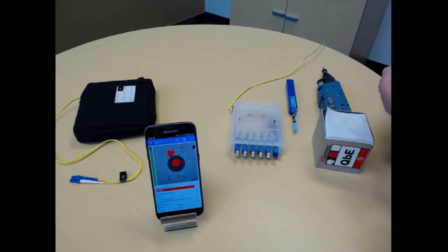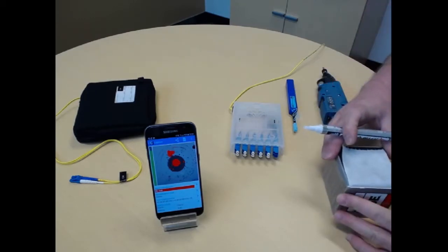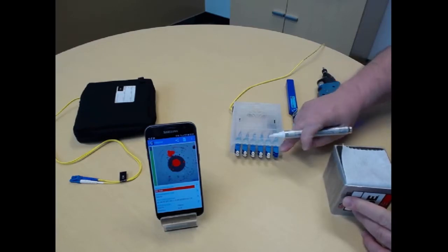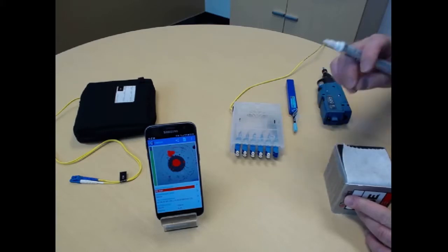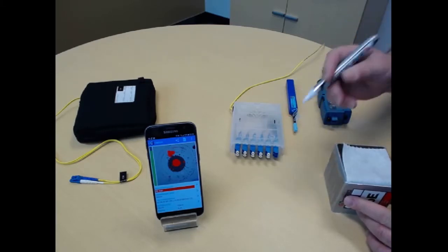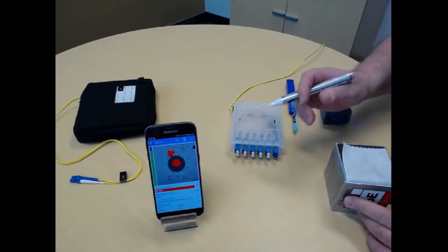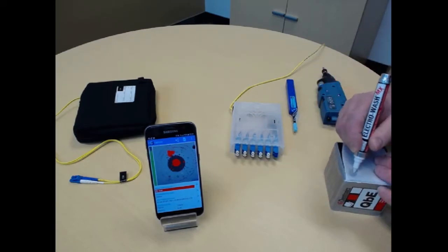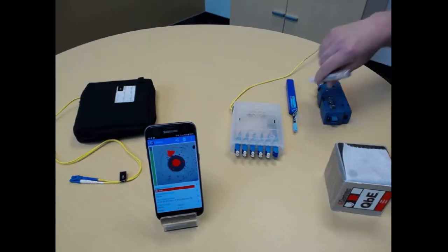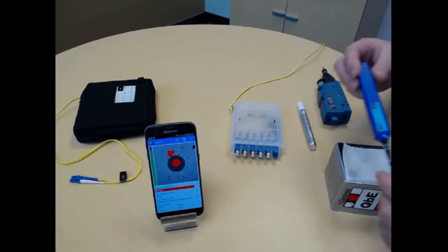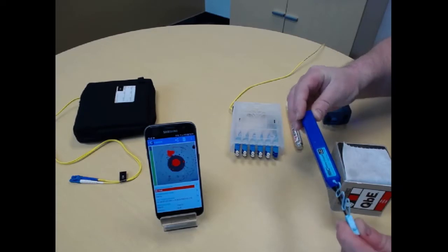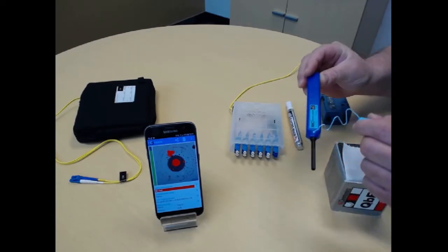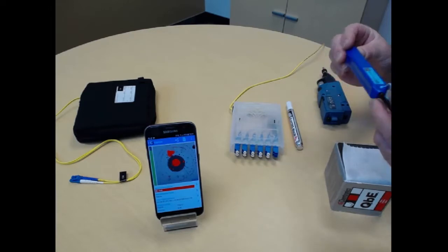So I'm using my electrowash pen. Because it's kind of tricky to put the pen inside the bulkhead connector and you have a high risk of inserting too much fluid inside the assembly, one good way, best practice, is still to wet a corner of the wipes, use your clicker, and remove the portion that is acting like a bulkhead.